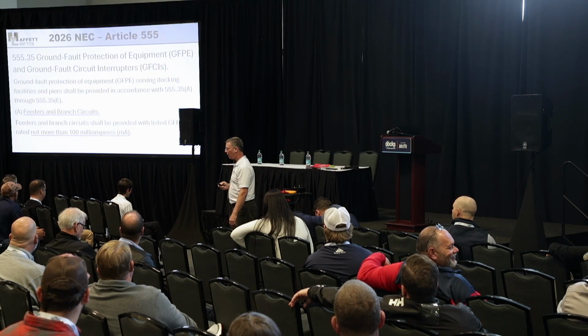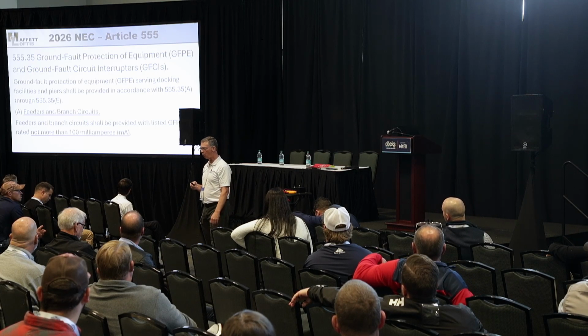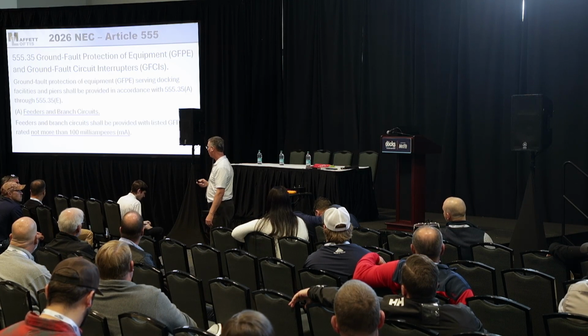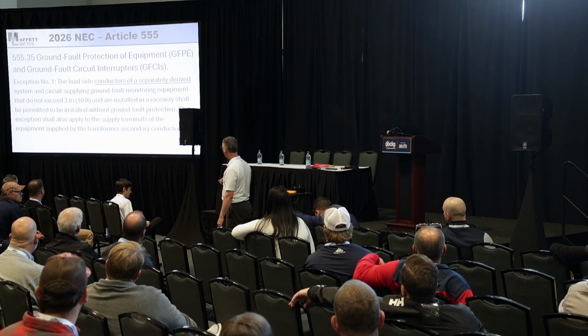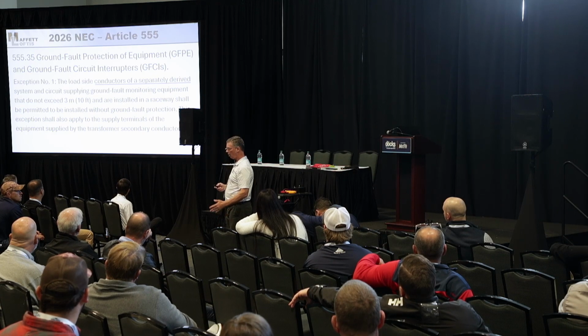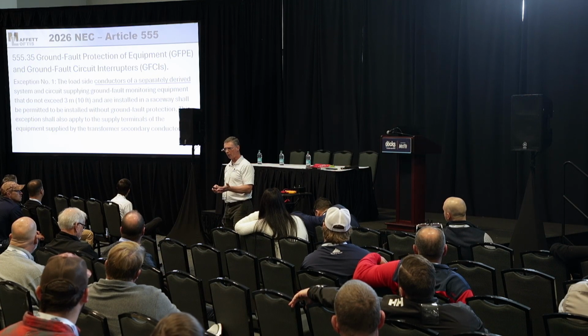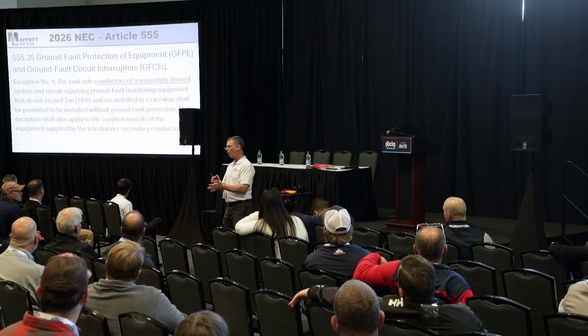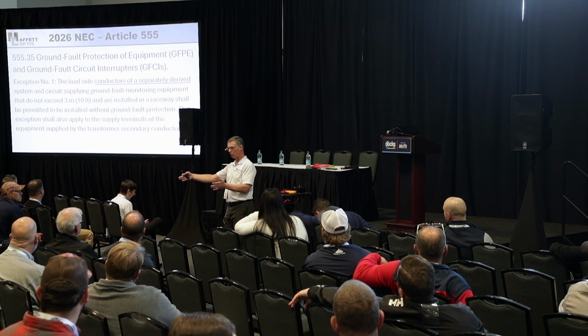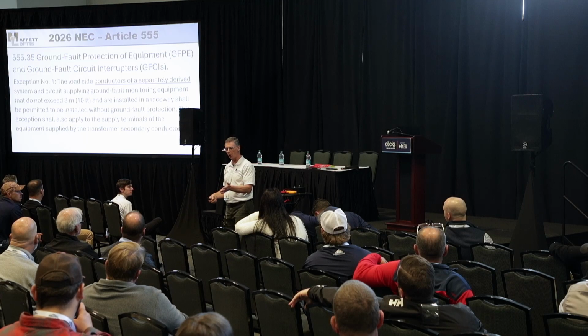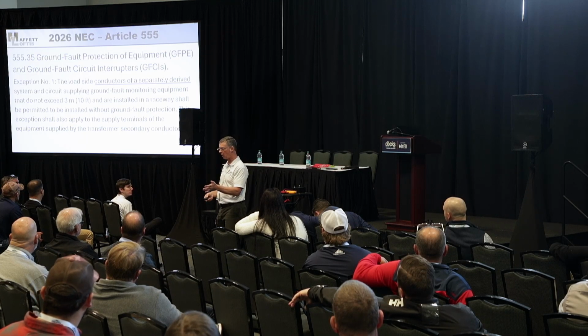However, there are exceptions, some wire on a marina that is not required to have GFPE. That is if it's a separately derived system, and a transformer is a separately derived system. The secondary wires from a transformer out to the panel do not have to have GFPE on them, because it's really hard to put 100 milliamp GFPE on the secondary side of a transformer.